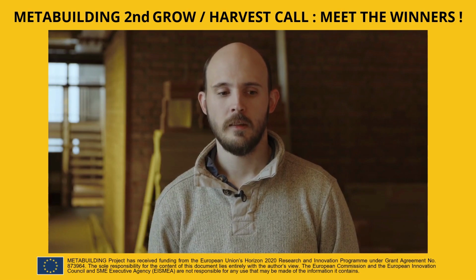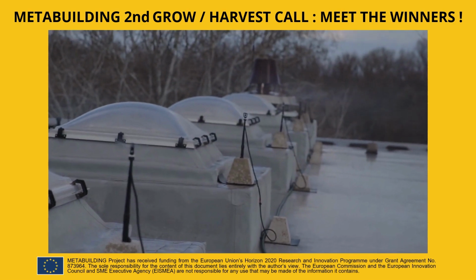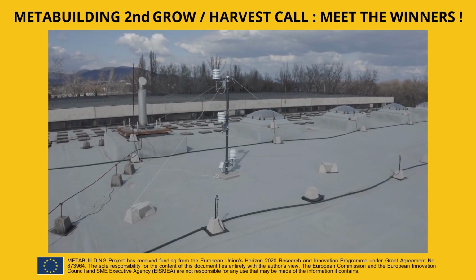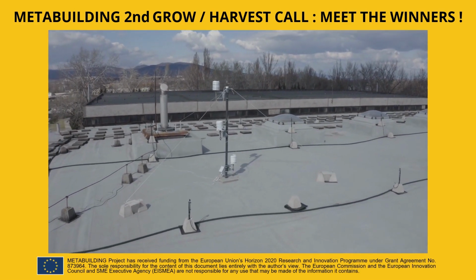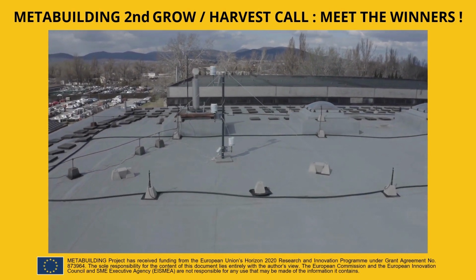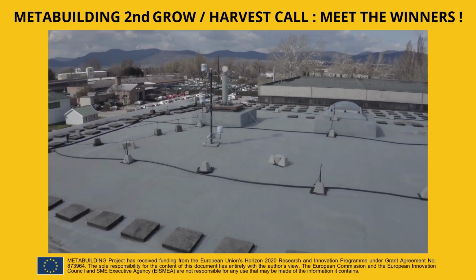The cooling system works by spraying a film of water onto the surface, which removes heat from the surface by evaporation. On the one hand, the monitoring modules are designed to monitor this process, for which humidity and temperature sensors above the roof are used, which are able to measure the air conditions at various points of the boundary layer that forms on the roof surface.